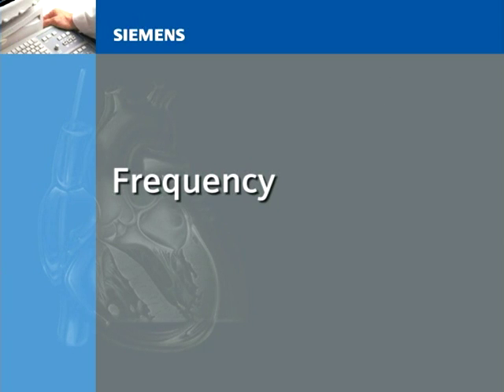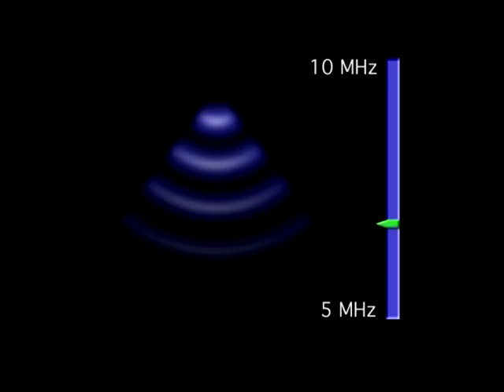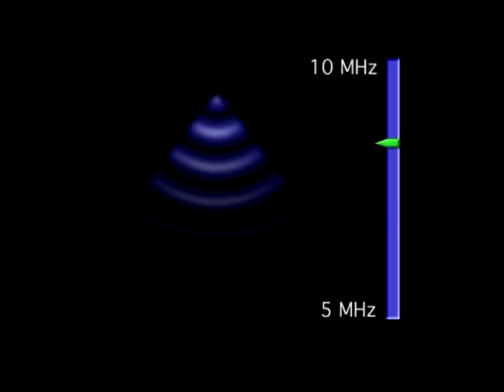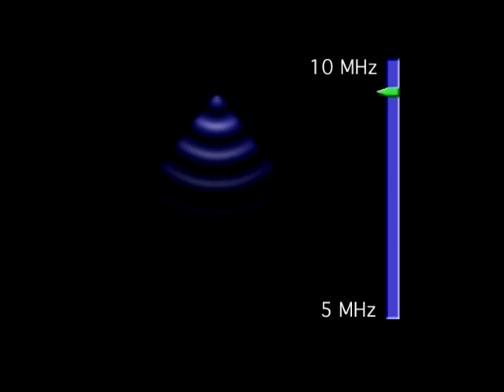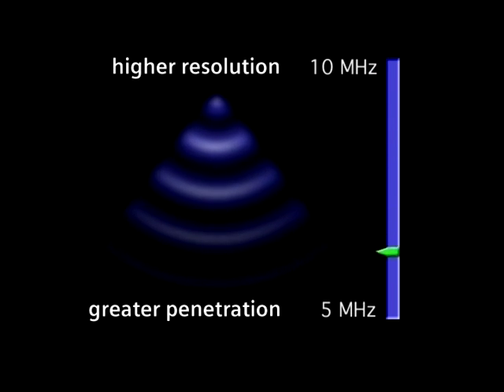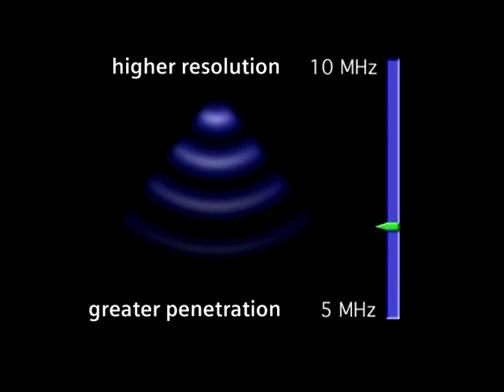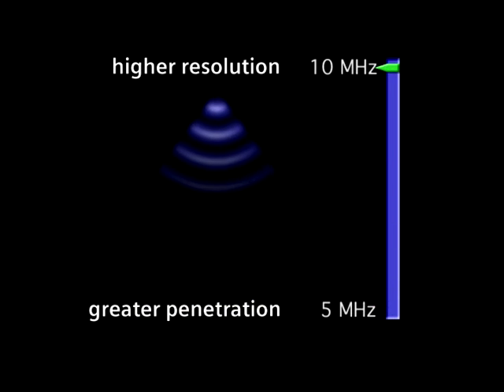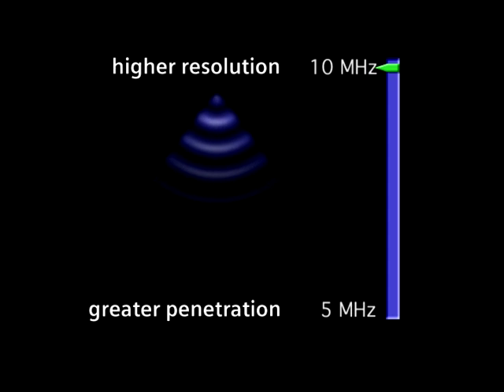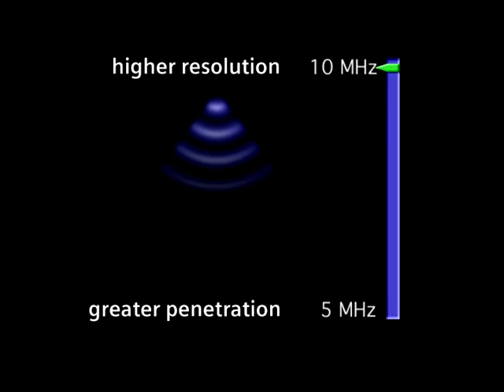Frequency. The imaging frequency you select affects both the resolution and penetration of the image. The higher the frequency, the higher the resolution or detail seen in structures. Frequency is inversely related to penetration of the ultrasound signal — that is, the higher the frequency, the lower the penetration. For the best image quality, use the highest frequency possible that maintains sufficient penetration throughout the entire image.